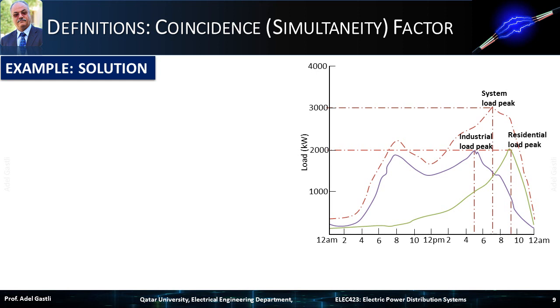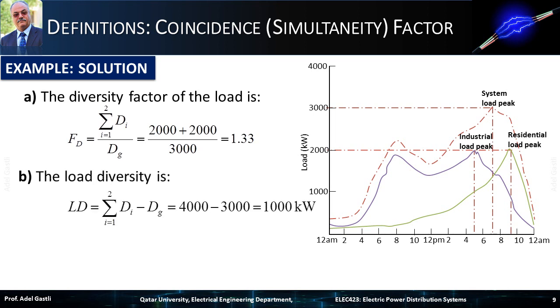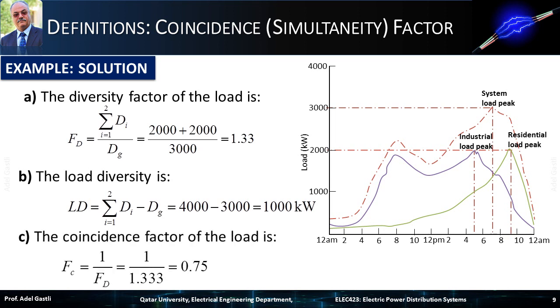To solve this example, we start by answering the first question about the diversity factor calculation. Since we have two similar peak loads — industrial and residential — of 2,000 kW each, and a total non-coincident load of 3,000 kW, we can find the diversity factor by applying its equation. This yields a diversity factor of 1.33. For the second question, the load diversity is calculated using this equation, giving a load diversity of 1,000 kW. Finally, the coincidence factor is determined as the inverse of the diversity factor, giving a coincidence factor of 0.75.